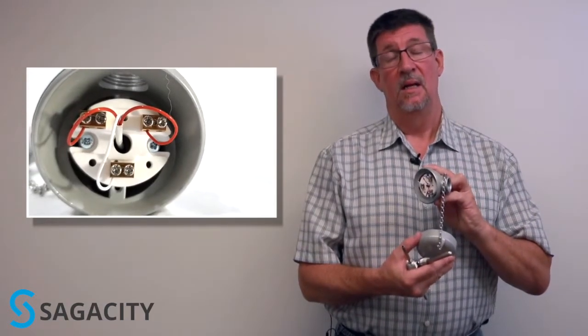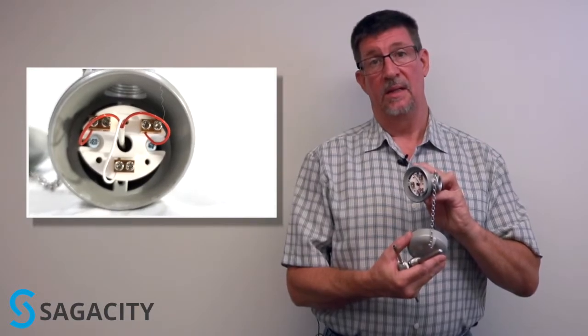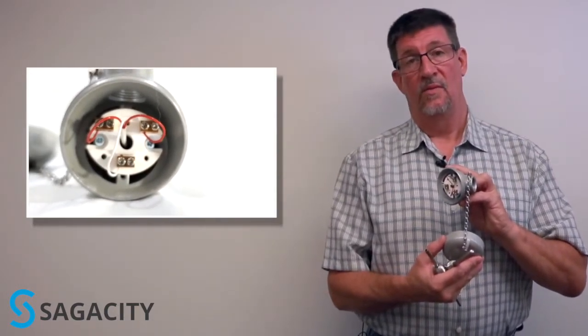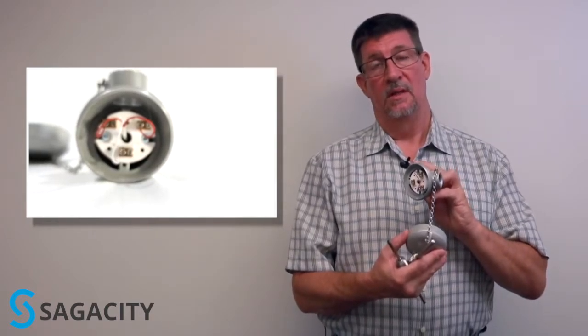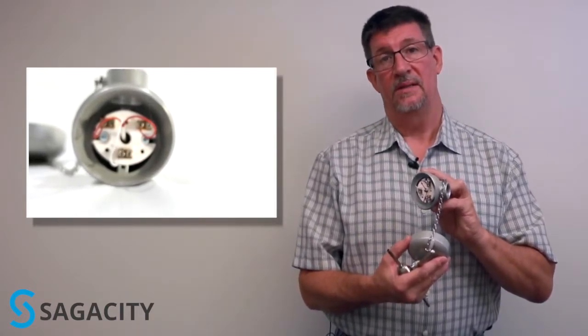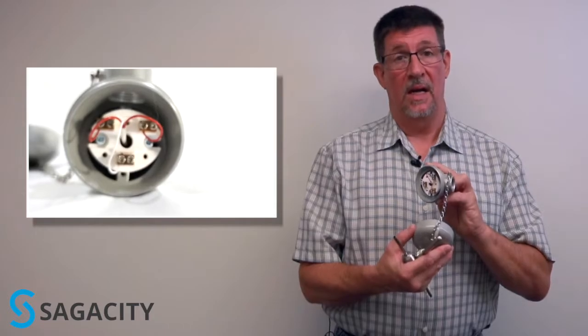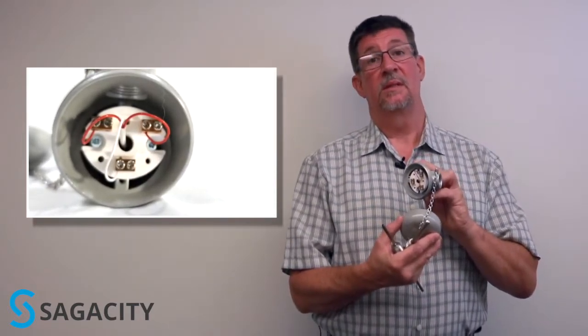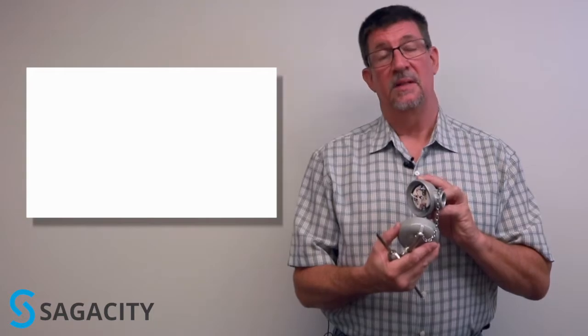In this particular case we have a junction box in the back with a terminal strip located in there so you can land your leads. For an RTD you typically have three or four wires. It's a non-polarized device that typically doesn't care how you hook it up as long as you get the resistance wires connected correctly back to your transmitter. The type of wire needs to be determined by the type of your RTD. Again the RTD manufacturer can make those recommendations.